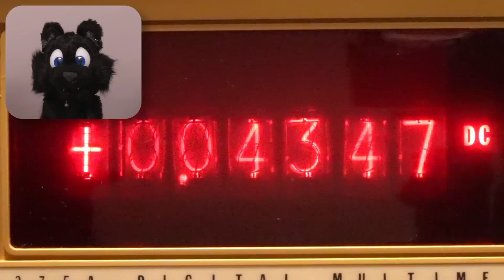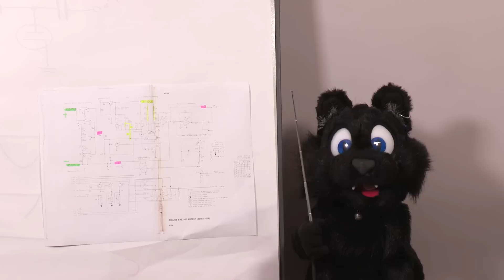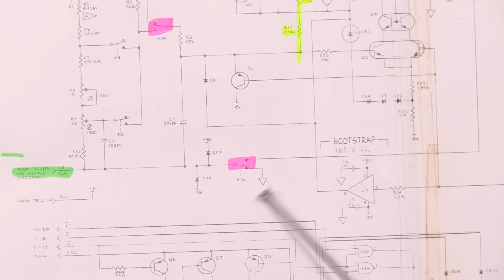So, back to troubleshooting it is. After following the signals all over and back again, I found out that one of the relays on the input attenuator board is not closing all the contacts. So in some ranges, the input signal has no ground. That explains the wandering signal.